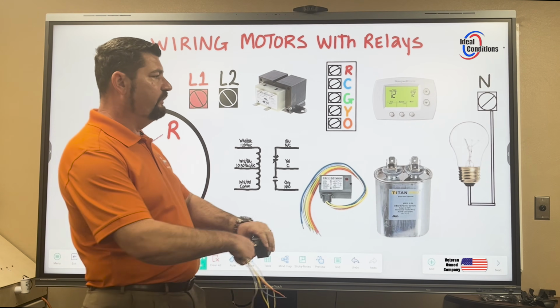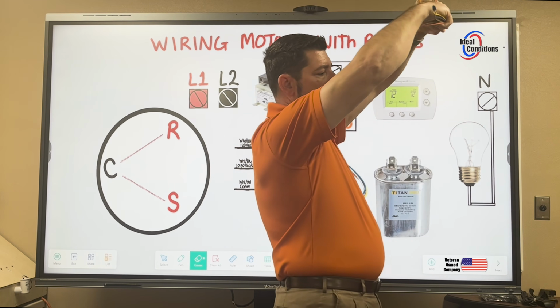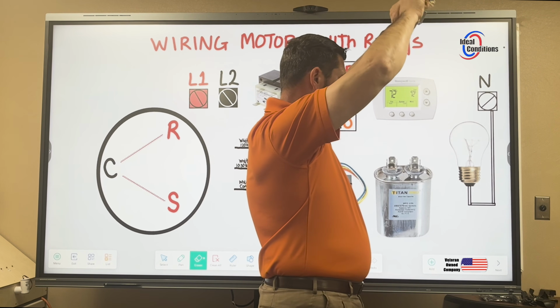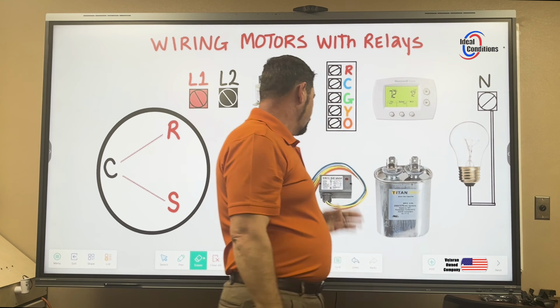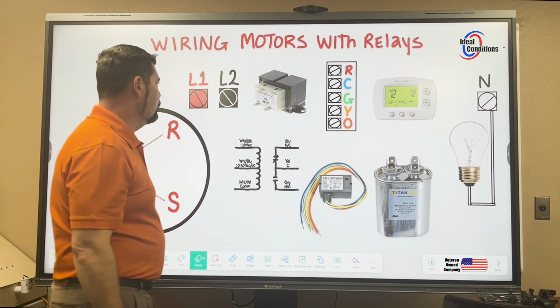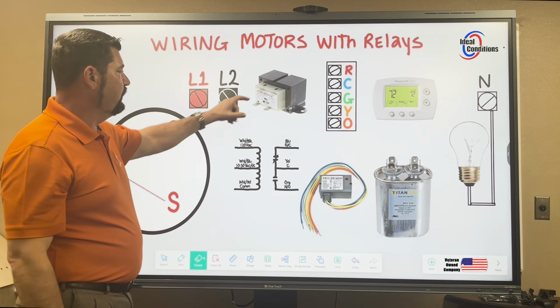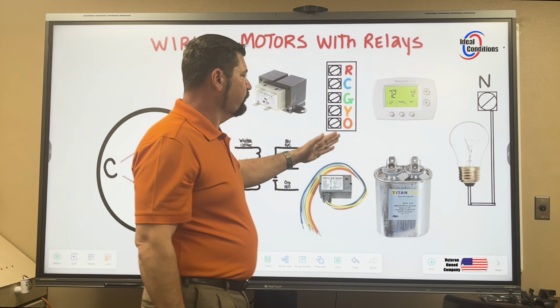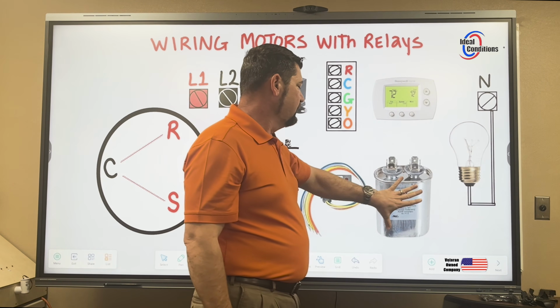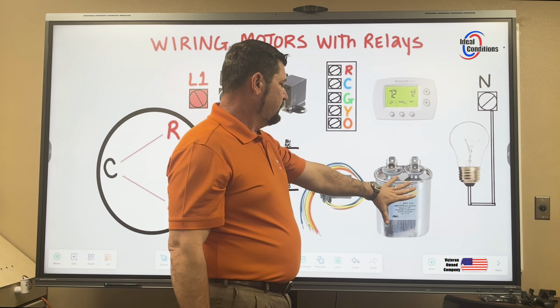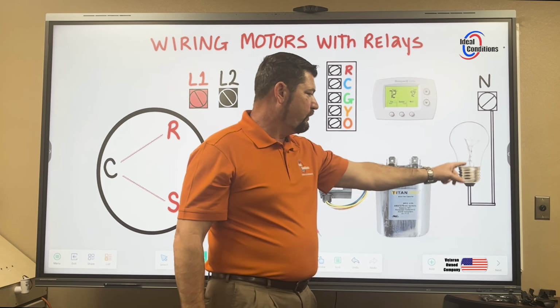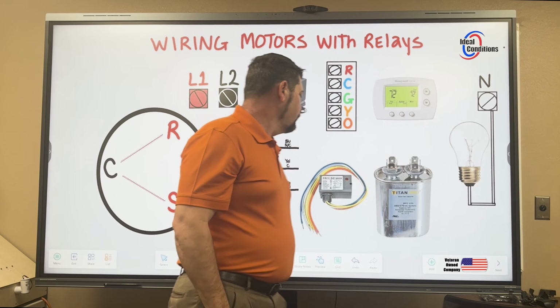A lot of this stuff is in a dark, cramped environment, and it's hard to see as it is. So at the end of it all, you need to have confidence in what these terminals do and what they're for. We have L1, L2 up here. We have a transformer, a low voltage terminal block, a Honeywell thermostat, and one run capacitor or light bulb that's already been pre-wired to neutral.